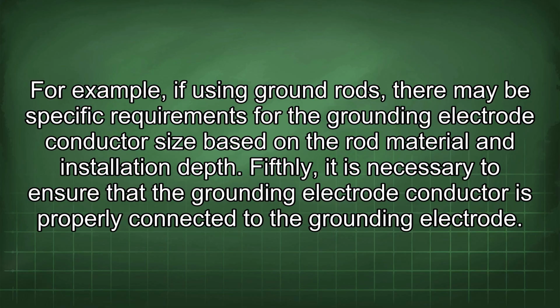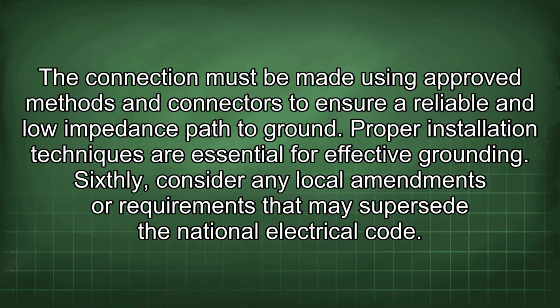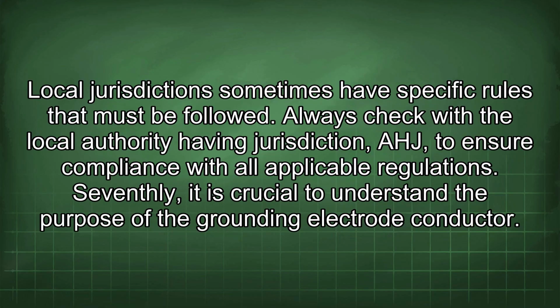Fifthly, it is necessary to ensure that the grounding electrode conductor is properly connected to the grounding electrode. The connection must be made using approved methods and connectors to ensure a reliable and low impedance path to ground. Proper installation techniques are essential for effective grounding. Sixthly, consider any local amendments or requirements that may supersede the National Electrical Code. Local jurisdictions sometimes have specific rules that must be followed. Always check with the local authority having jurisdiction, AHJ, to ensure compliance with all applicable regulations.